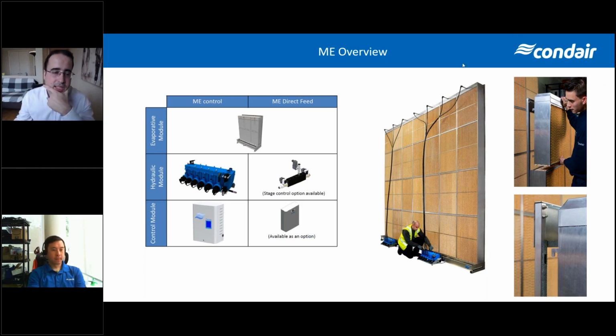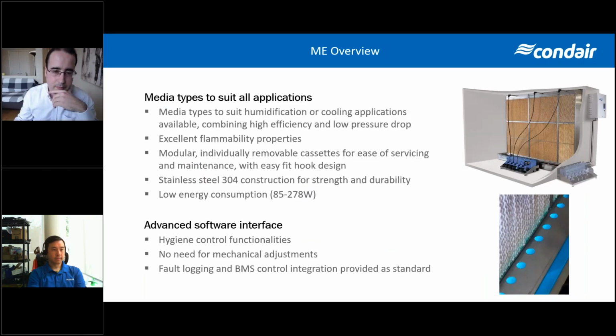One of the neat things about our system is the media. The media you can see on the right is always in a stainless steel frame with an interlock mechanism. This makes it easier to assemble, and there is no risk of collapsing over time, especially in a large XL system. Like I said, we have different types of media: 4, 6, and 8-inch. We also have different flute angles, 30-30 and 45-15, depending on the efficiency you want. It's a UL 900 media.